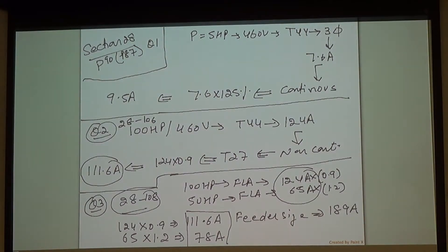In a continuous motor, you pick your highest FLA and get that multiplied by 125 and add the rest.